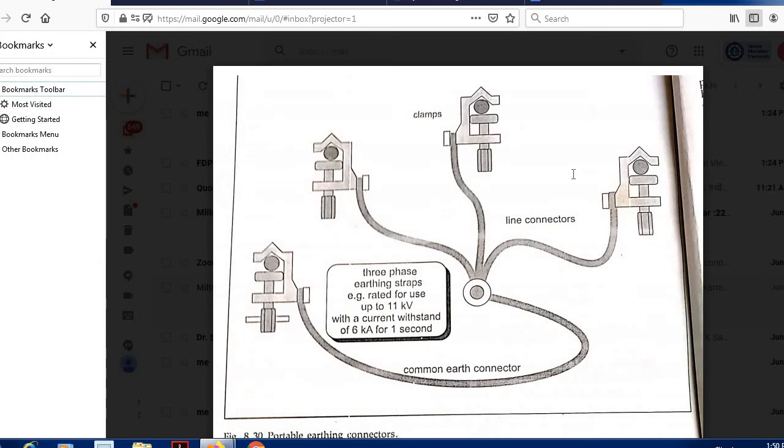Now, is it ready for taking the insulation resistance? If I operate the Megger, can I take the insulation resistance? Will I get the right value? No, because the phases are already connected to the ground. When we are measuring, we are checking between conductors, but the conductor is already connected to the ground, so it will give you a wrong value. So before this we have used the straps just for connecting the Megger probe.